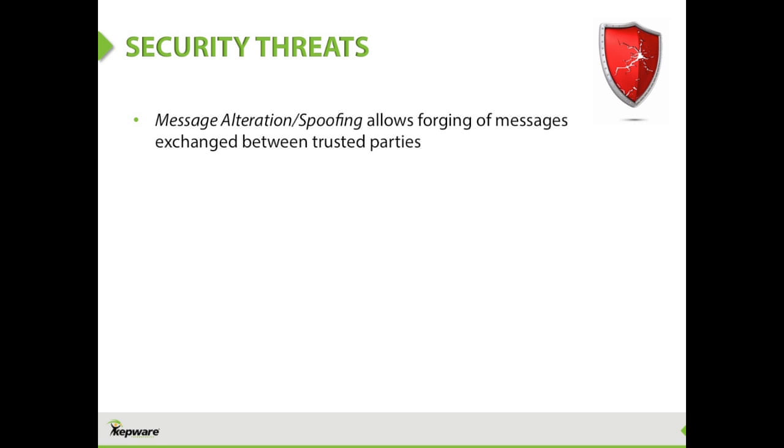We'll talk about another one, message alteration and spoofing. It's kind of like malformed messages, but it's a little different. A lot of the protocols that we support, Modbus, DNP, that are used in control systems, and many more, they're publicly documented. It's trivial for me to go online and Google this protocol and understand, okay, this is what the packet looks like, this is the information in it. When I have that information, I can then craft custom messages based on the protocol, and like malformed messages, I can start to tweak bits and pull things out of the ordinary.